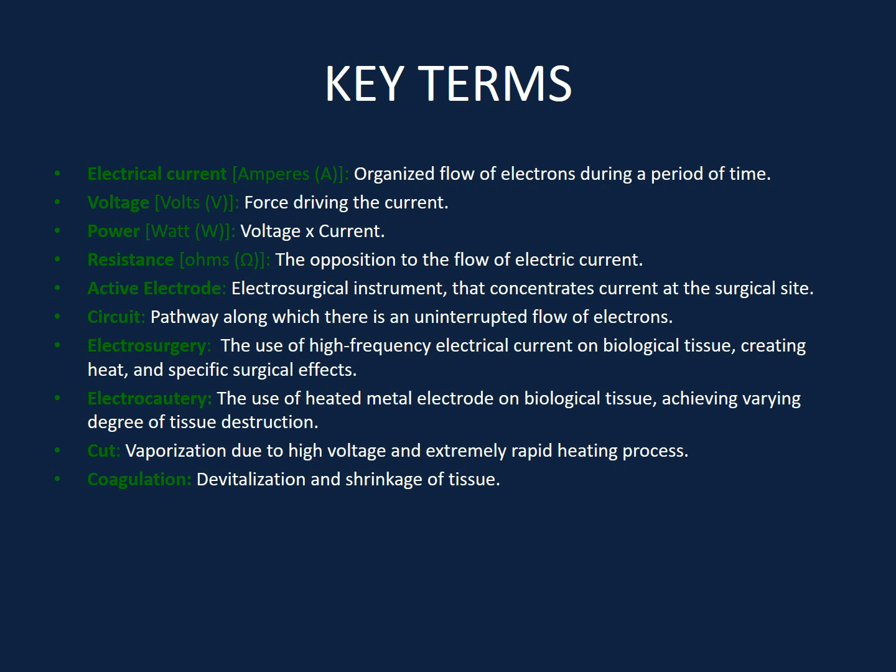Electrocautery differs from electrosurgery in that an electrical current heats a metallic probe that is then applied to tissue. In cutting, the tissue is rapidly heated above 100 degrees Celsius using high voltage, causing vaporization and cellular rupture. In coagulation, the tissue is heated more gently, between 60 to 100 degrees Celsius, causing devitalization and shrinkage of tissue.